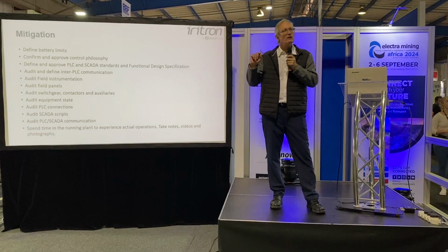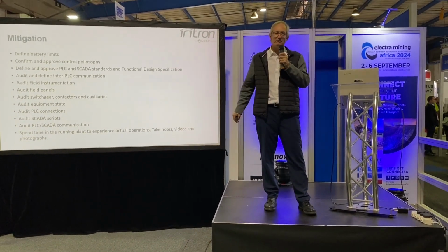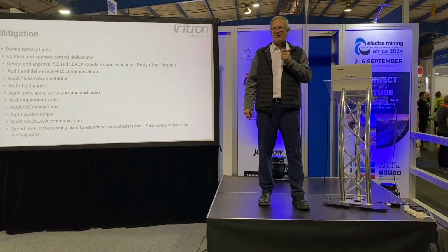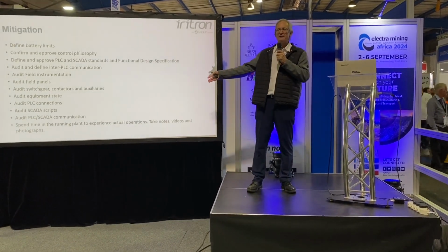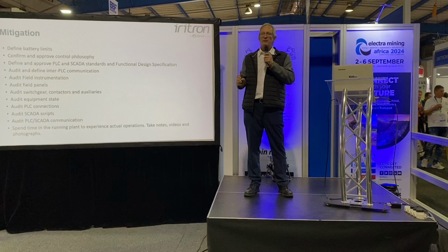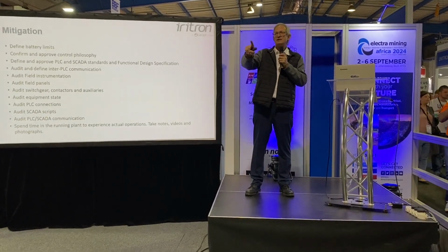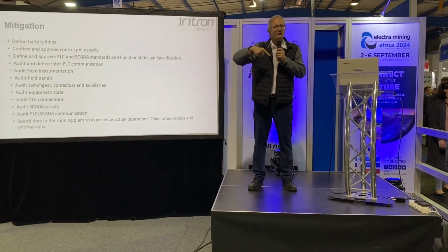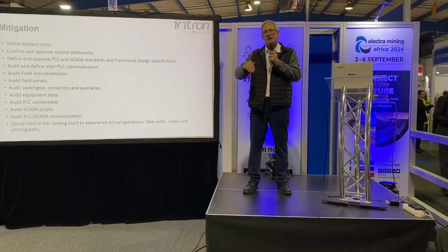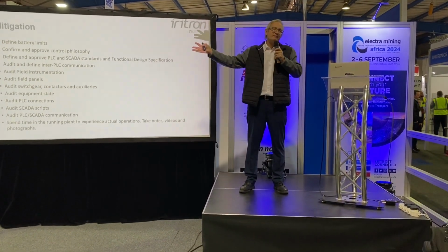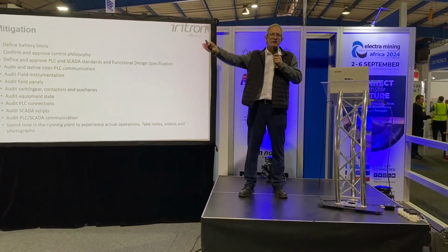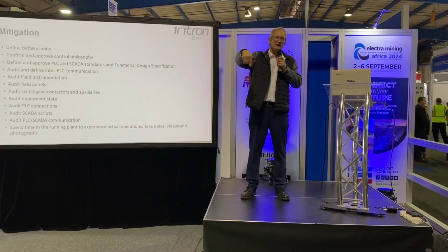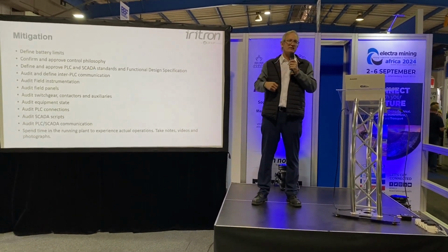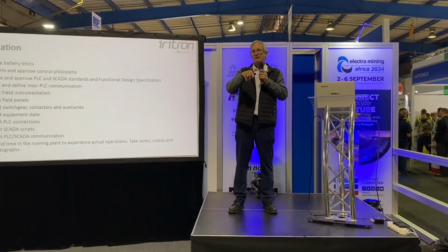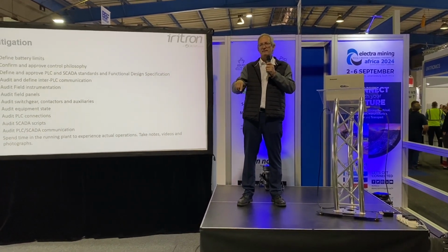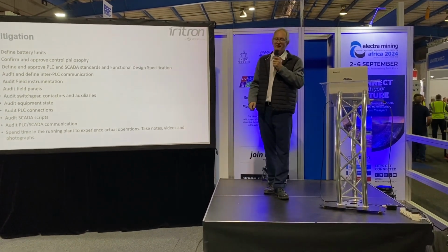Because remember, we're only duplicating what we have now. And everything is working. So when you're looking at the SCADA and there's a lot of red equipment and they say, well, don't worry about that. It's actually running. It's just the sensor that tells me the running signal is not coming back, but we know it's running. When you touch it, you own it. You have to make sure that the instrument that tells it that it's running gets fixed. At your cost, potentially, but definitely at your time, because it will become your problem.